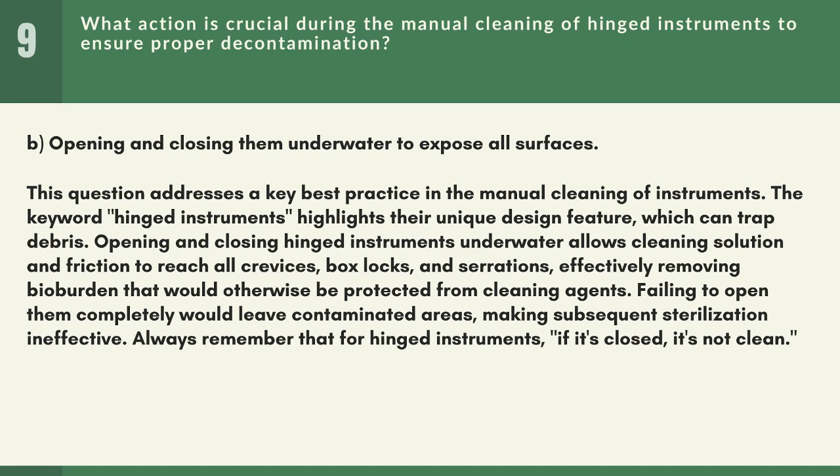Answer: B. Opening and closing them underwater to expose all surfaces. This question addresses a key best practice in the manual cleaning of instruments. The keyword hinged instruments highlights their unique design feature, which can trap debris. Opening and closing hinged instruments underwater allows cleaning solution and friction to reach all crevices, box locks, and serrations, effectively removing bioburden that would otherwise be protected from cleaning agents. Failing to open them completely would leave contaminated areas, making subsequent sterilization ineffective. Always remember that for hinged instruments, if it's closed, it's not clean.